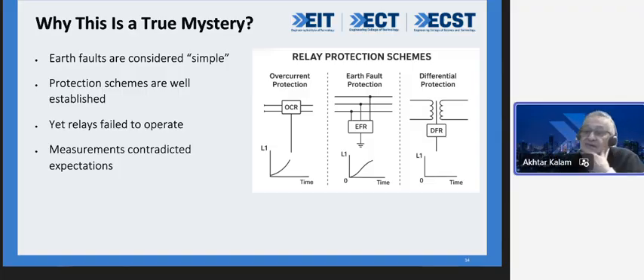And what is the reason for such type of failures? I'll give you a few. The first one I want to talk about is measurements, and the measurements that were contradicting the expectation. The first device I want to talk about is the instrument transformer. That is CTs and VTs, current transformers and voltage transformers.